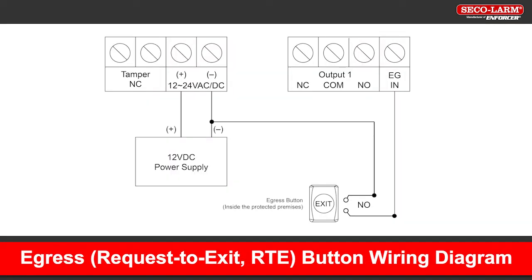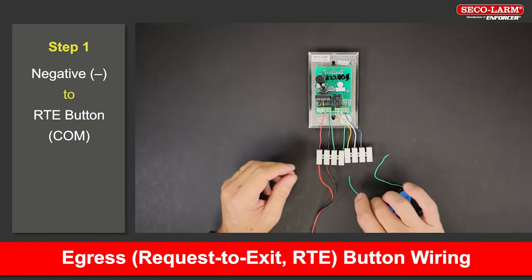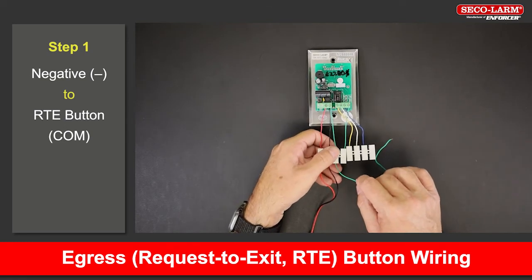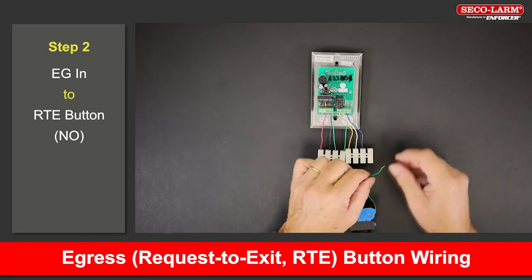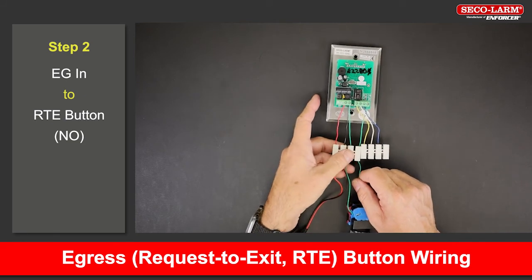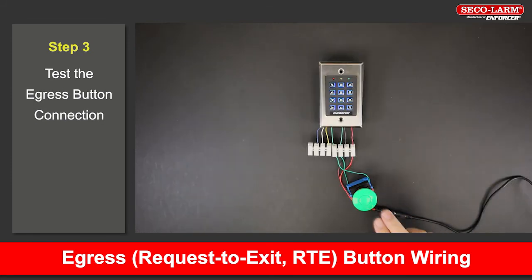Next we'll hook up the egress button. Note the diagram here before we show the steps. To wire an RTE button — request to exit — to the egress terminal: Connect the negative terminal to the request to exit button's common. Connect the keypad's EG IN to the request to exit button's normally open. Press the button and the relay will trigger.